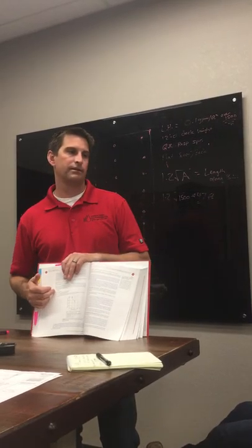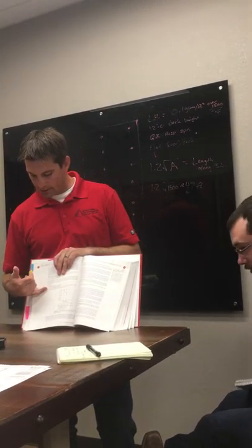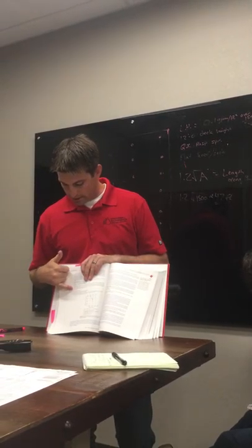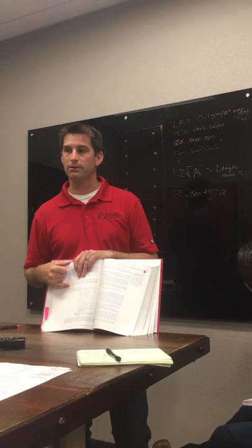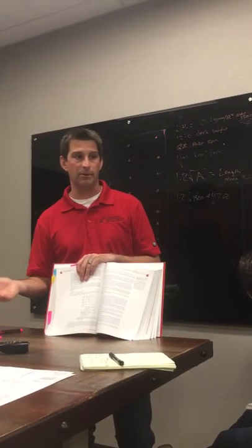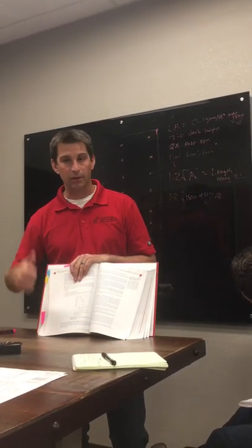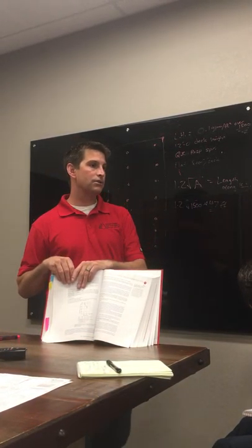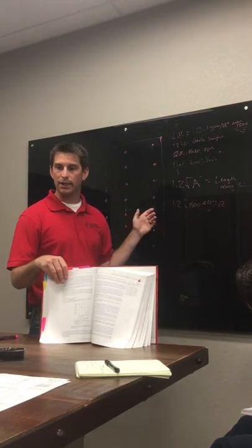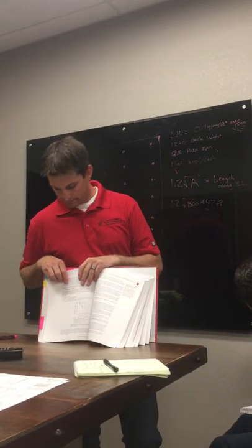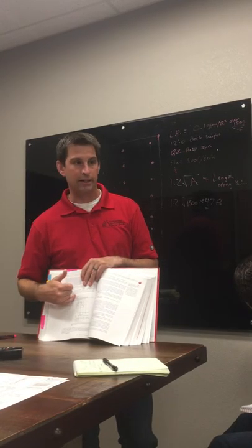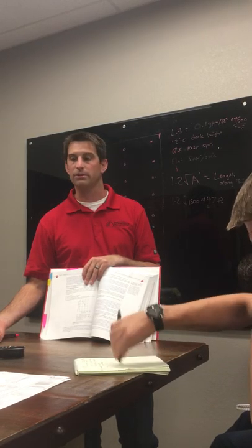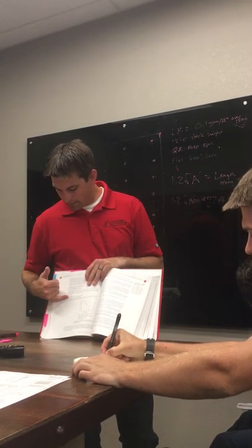And it'd be bad to tell you this without making sure you understood these things. So there are other things that apply. So we already said ceiling heights and the sprinklers themselves. It also has to be a wet system. Wet sprinkler system, you can't use it on dry because the dry system is going to be way delayed. So we actually have to increase that. But a wet system, light and ordinary occupancy. So I can use quick response reduction in ordinary or light, but I can't use it on extra hazard. Okay. And it says light and ordinary. It doesn't say ordinary 1 or ordinary 2, so it applies to both ordinary 1 and 2, just as ordinary has your occupancy. 20-foot max ceiling height.